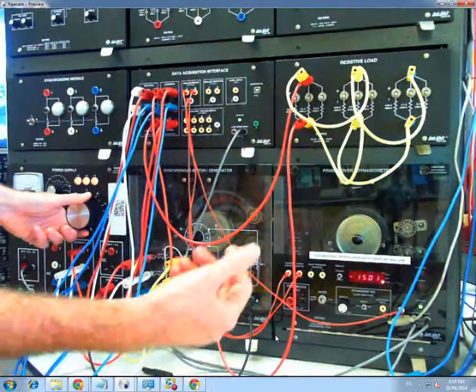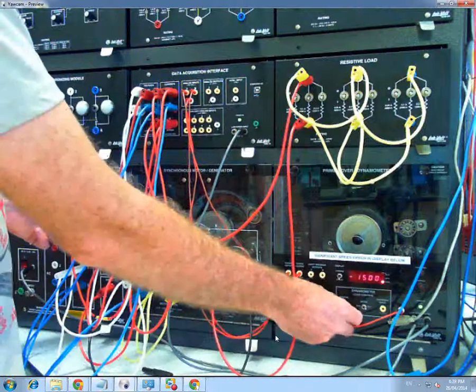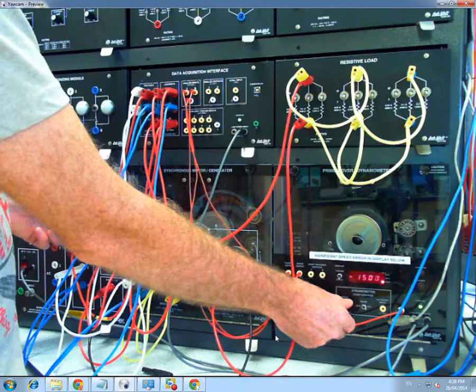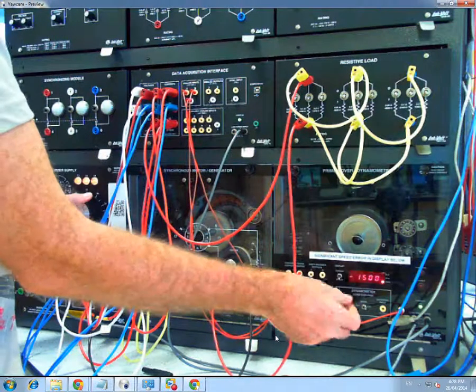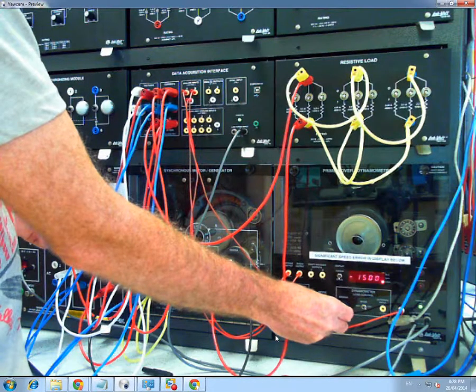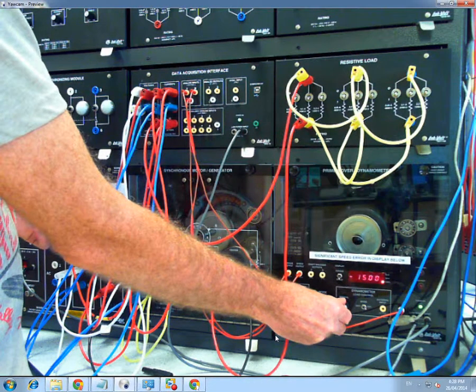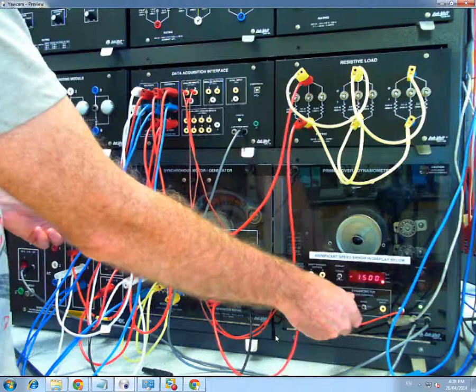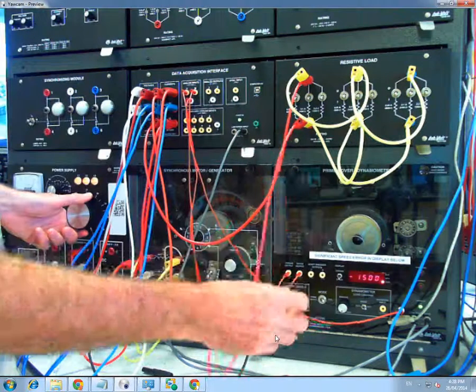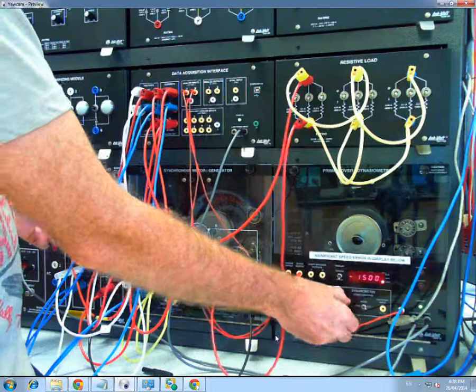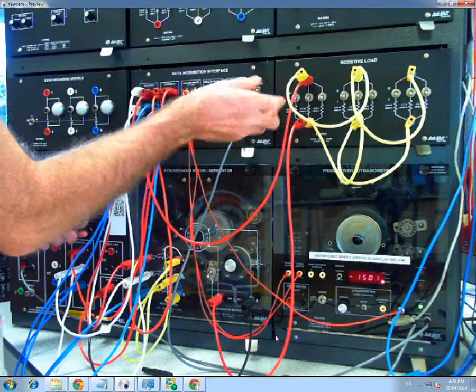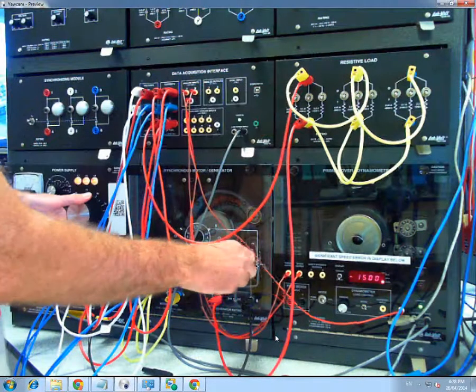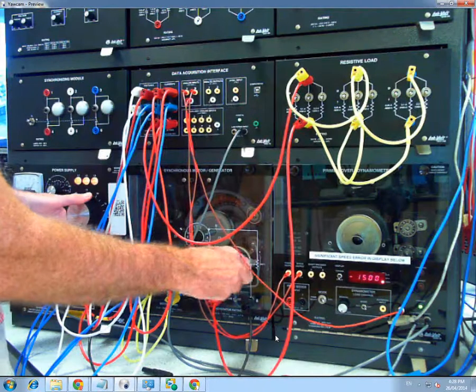Now, at the synchronous motor, once it's running in sync, you'll find that you can load it up and it will maintain the same speed until it reaches a certain braking torque. Now, in this case, the field winding excitation is strong enough that I can't reach that braking torque. But if I added more resistance into the circuit, so for example, I could wind this up to the opposite extreme.